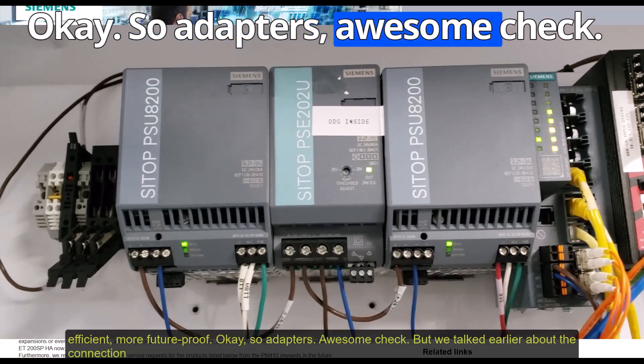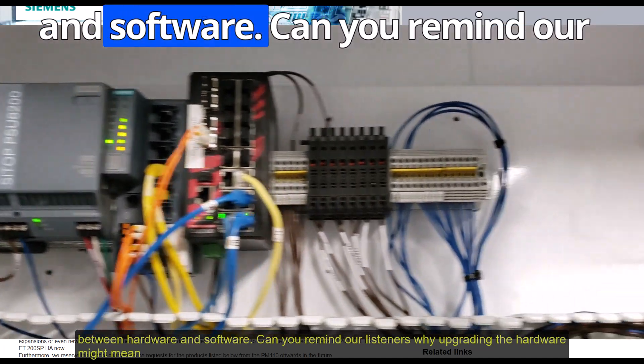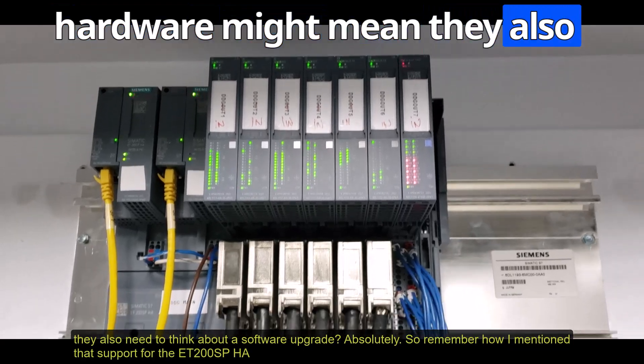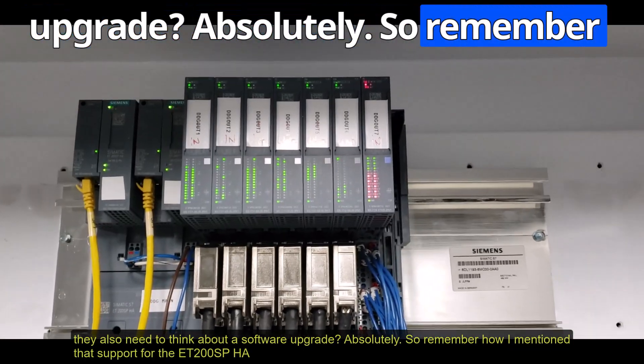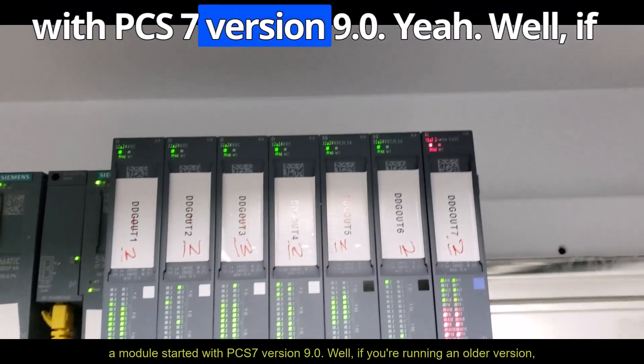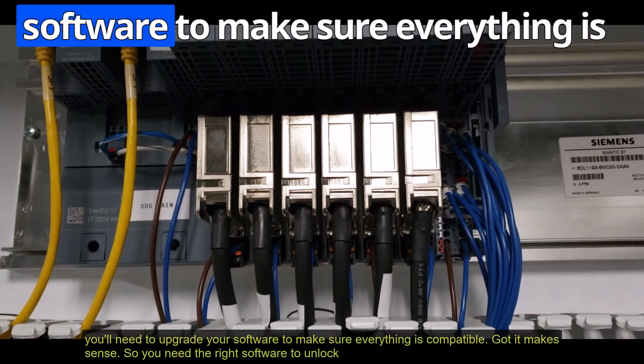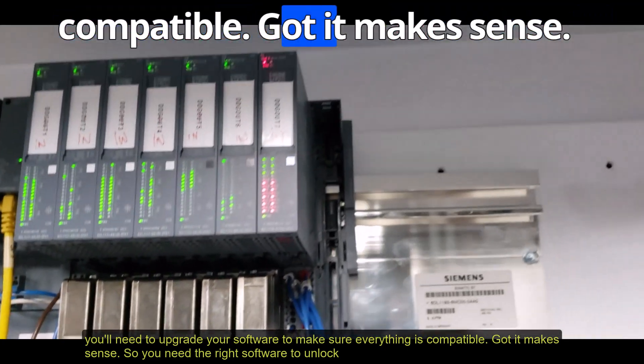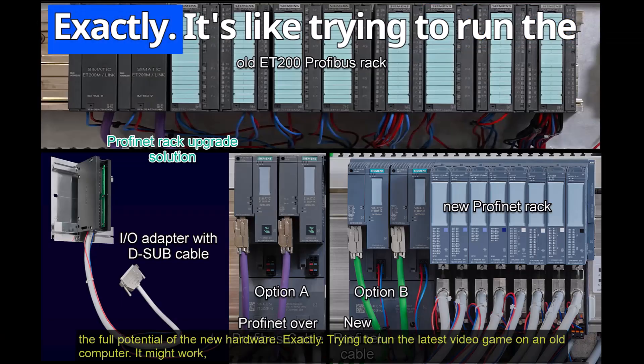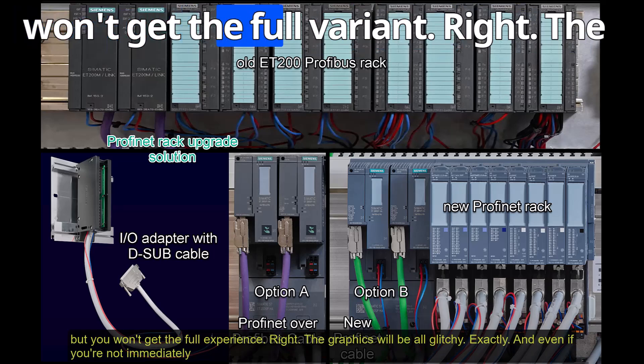Now, the connection between hardware and software: upgrading the hardware might mean they also need to think about a software upgrade. Support for ET200SPHA modules started with PCS7 version 9.0. If you're running an older version, you'll need to upgrade your software to make sure everything is compatible — you need the right software to unlock the full potential of the new hardware.